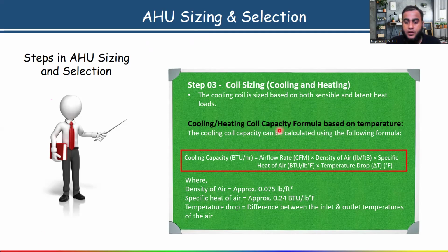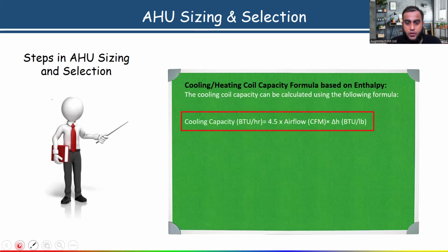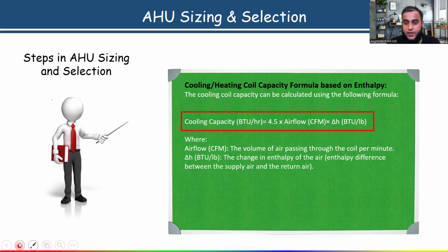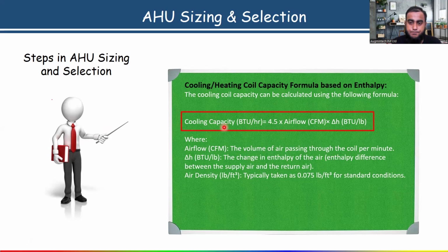So this is the first formula, and it is based on temperature. In the same way, if you want to find the cooling or heating coil capacity based on enthalpy, we have a formula for that too. The cooling capacity in BTU is equal to 4.5 times airflow in CFM times delta H. Airflow means the volume of air passing through the coil per minute. Delta H is the change in enthalpy of the air. Is it clear? And air density is given here. So we have to use this formula. This factor 4.5 comes from the conversion factor, so don't worry about that. Just remember the concept. So I have shown you two formulas, one based on temperature and one based on enthalpy. Is it clear?